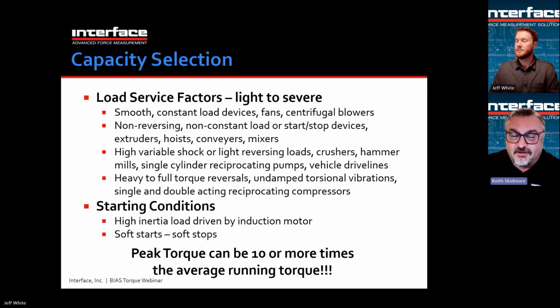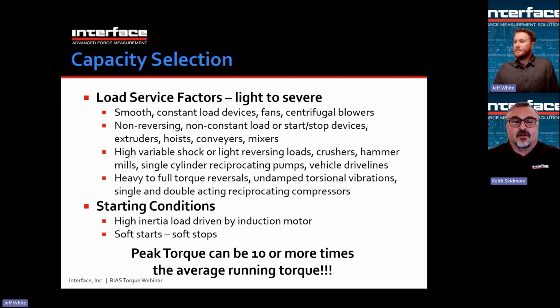And then you have to consider starting conditions. If you start up an electric motor and just apply power to it, it'll start to spin, and the torque it can produce during start conditions can be much, much greater than the actual average running torque.